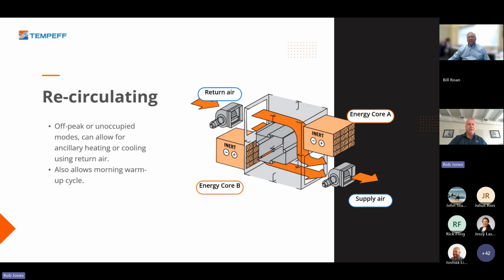We also have a recirculation mode as well. This is for low occupancy or no occupancy of the building, where the building energy, whether cooling or heating, is being returned right back to the supply air. So again, there's no energy recovery going on. What we do here is we slightly crack open our shutoff dampers. This creates a positive pressure around the damper and a negative pressure across our 2 cores. That means that that air, that energy, will naturally migrate to our cores and charge them.